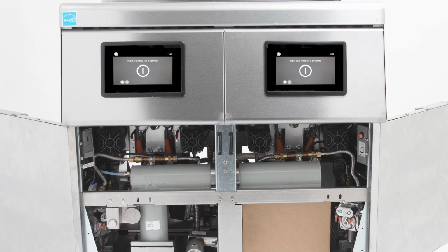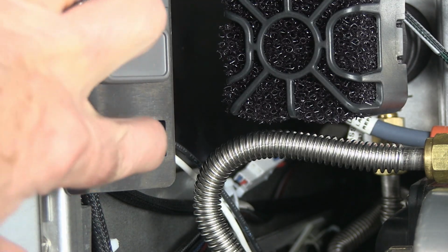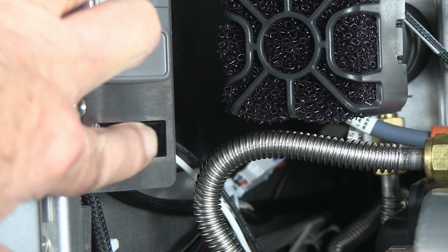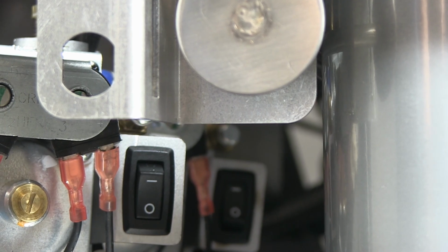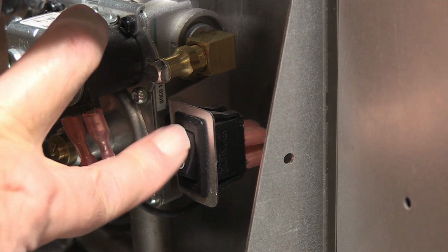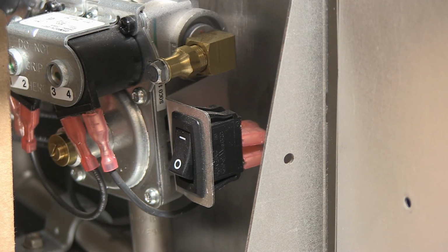If the fryer needs to be reset for any reason, locate the rocker switch inside the left door. Press and hold the switch down for 1 minute. Each gas valve has an on-off switch. Ensure the valve is turned on, the dash position depressed.